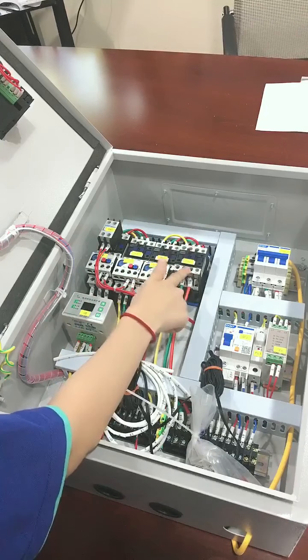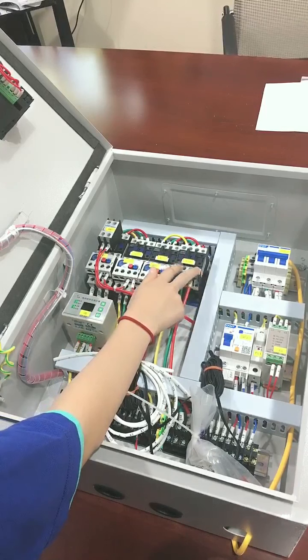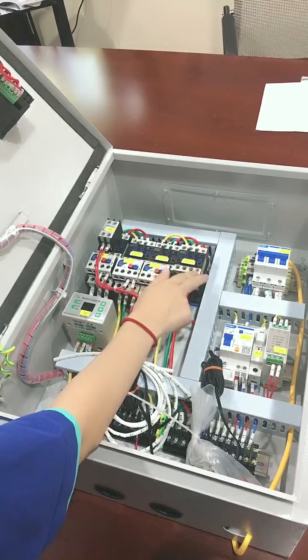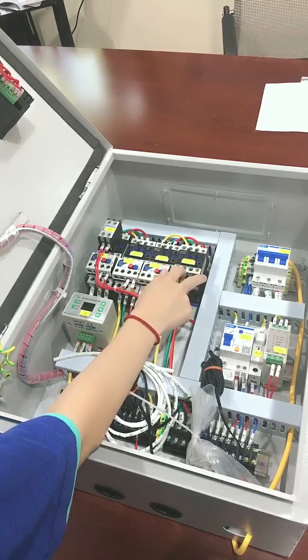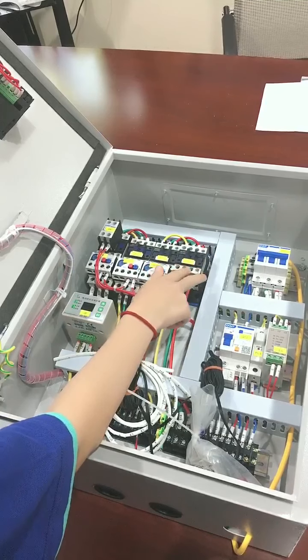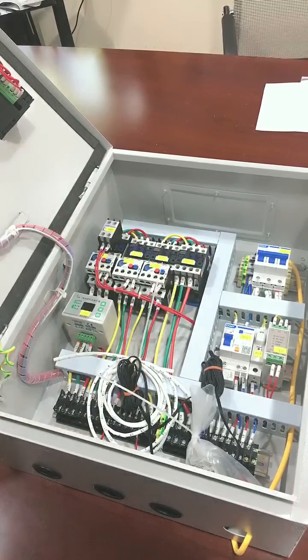And then next to the evaporator model, this is the function for defrost. Defrost is an important part of a cold room system. Any ice building up on the outside heat exchanger reduces the airflow across it, which will affect the efficiency.